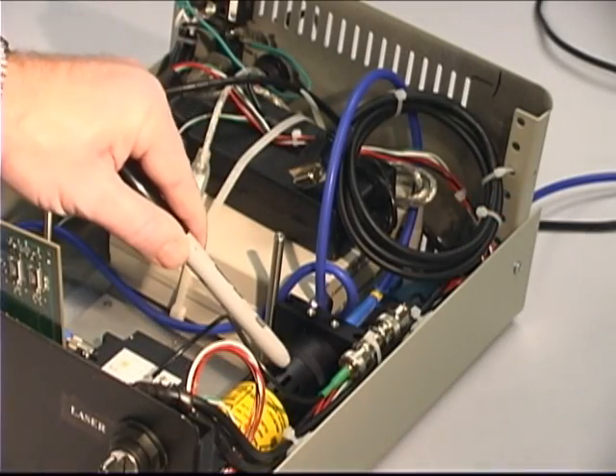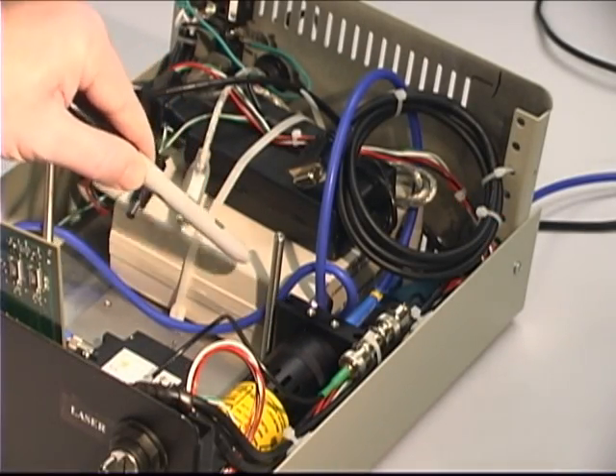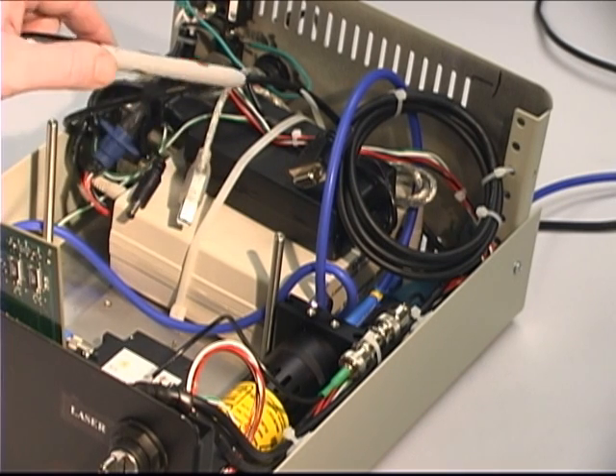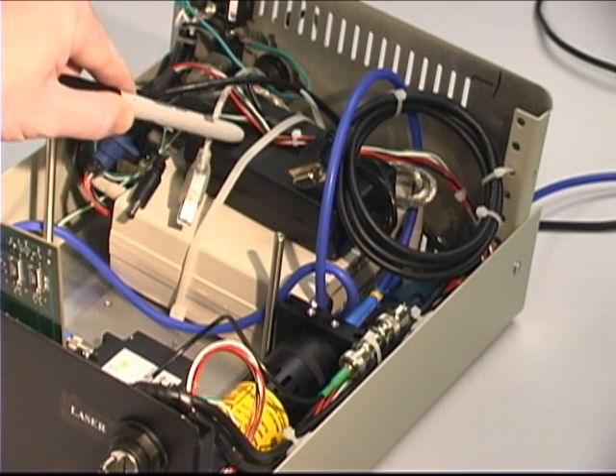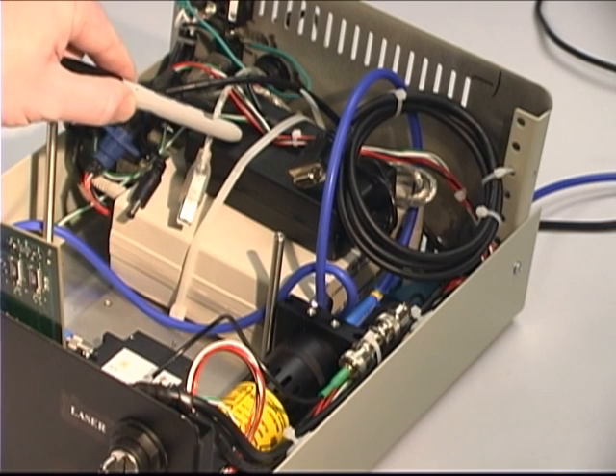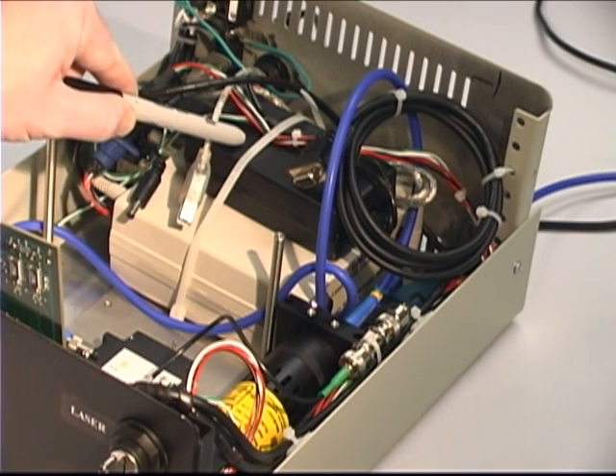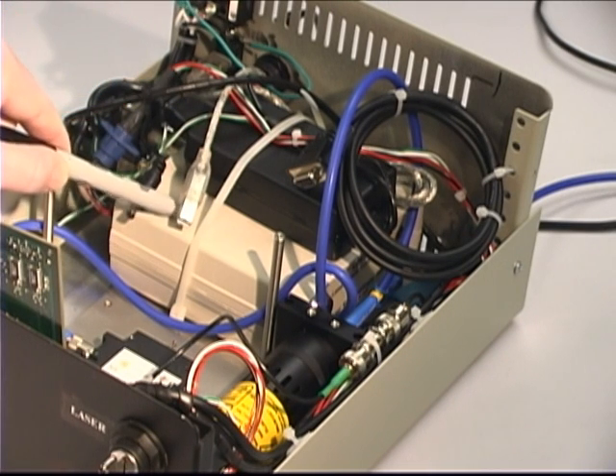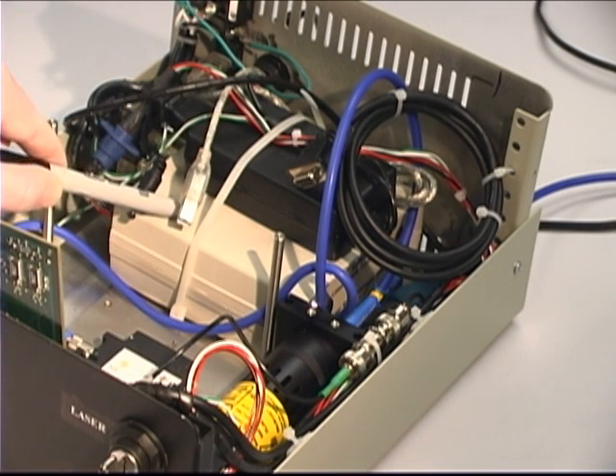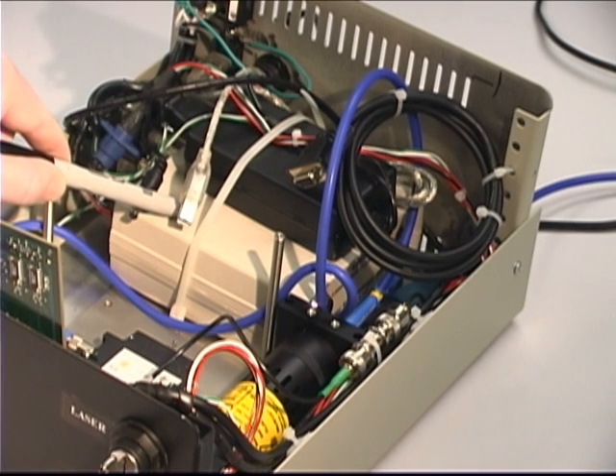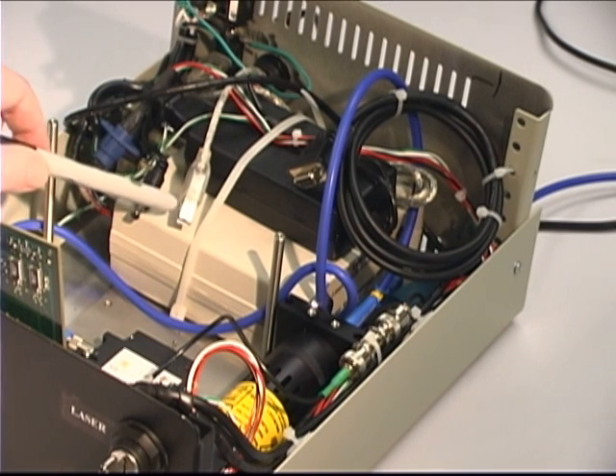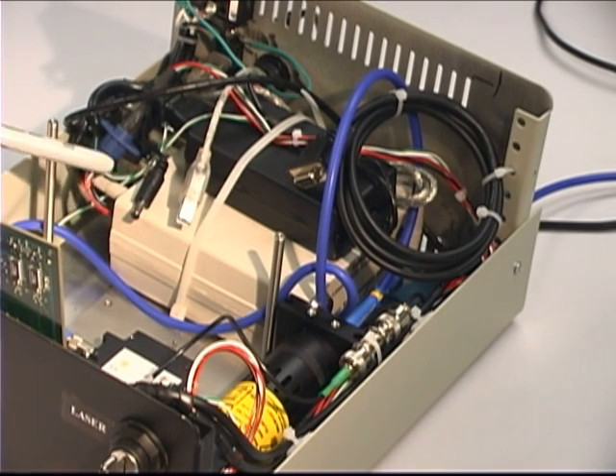The only power requirement for the LIF unit is a standard 110 volt AC. An AC-DC power supply supplies low-level voltage to the analog-to-digital converter and detector electronics. The laser power supply provides the necessary voltage levels to the diode laser. The modulation voltage is set by software and is provided via one of the DAC channels on the analog-to-digital converter. This modulation voltage is input into the laser power supply unit.